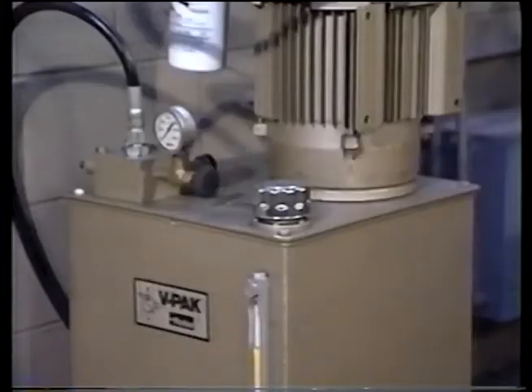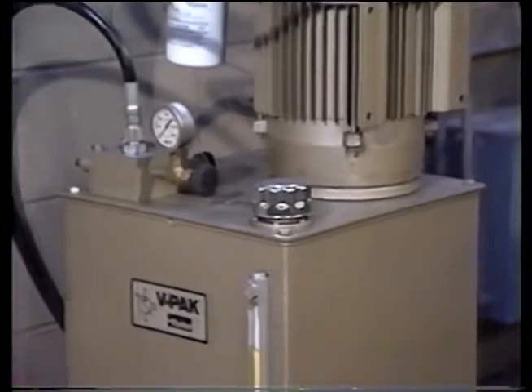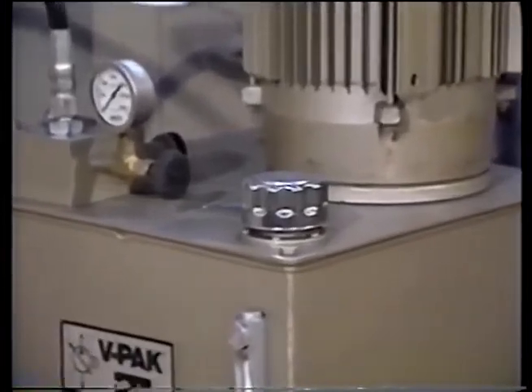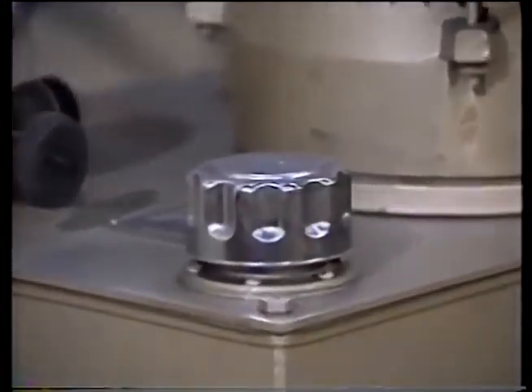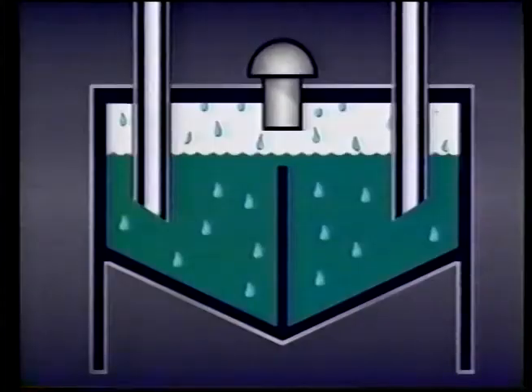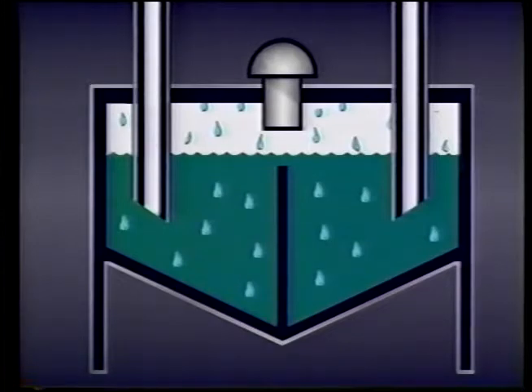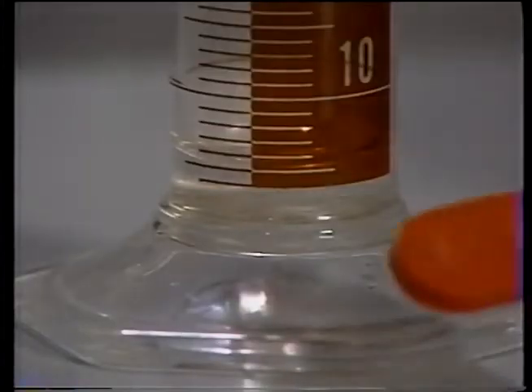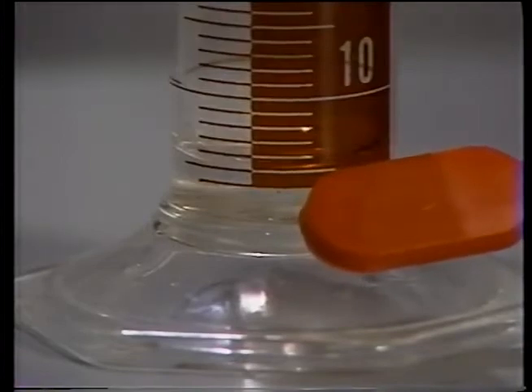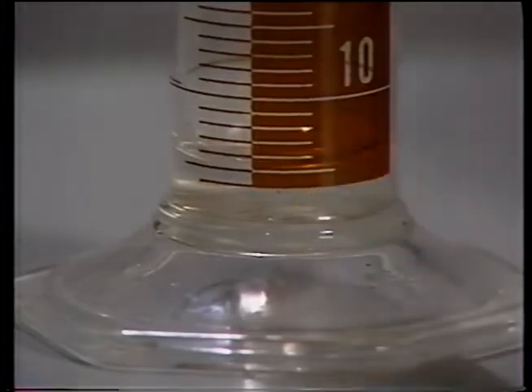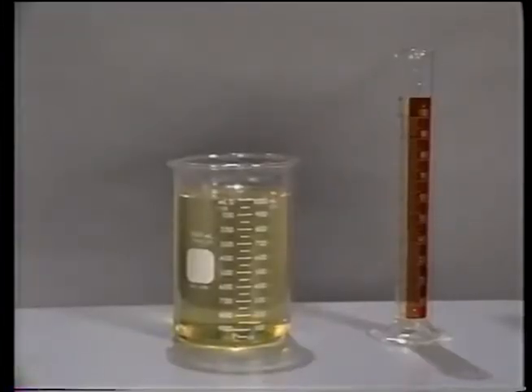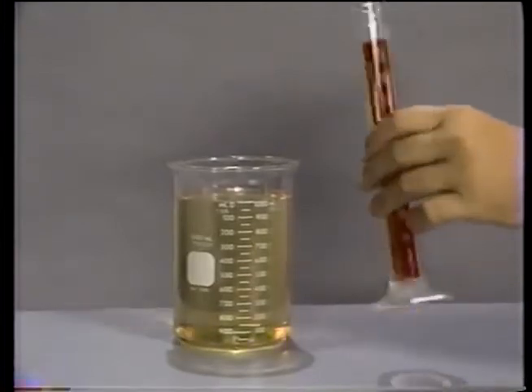Rust is usually formed when water condenses on exposed metal surfaces. Moisture-laden air is constantly drawn into the reservoir through the breather cap. When the system cools down, water vapor condenses out on the reservoir walls and eventually makes its way into the fluid. Even small amounts of water in petroleum-based hydraulic fluids — less than half of one percent — can start to rust the system.